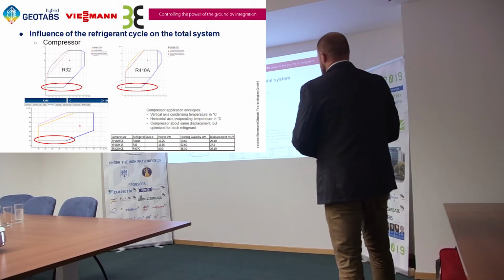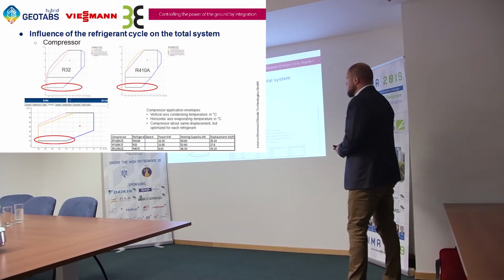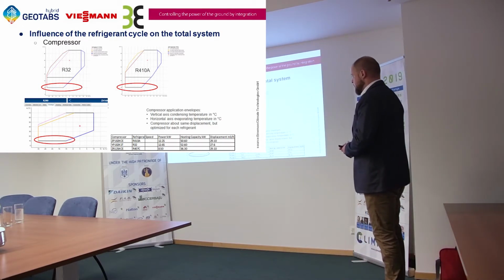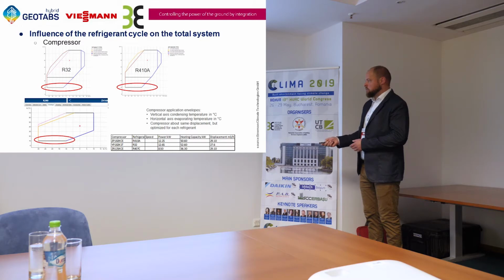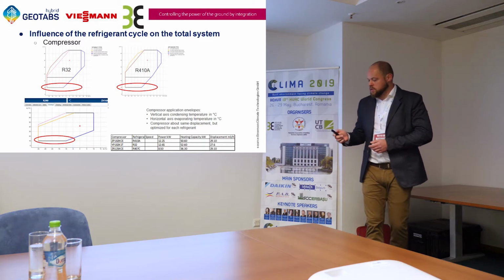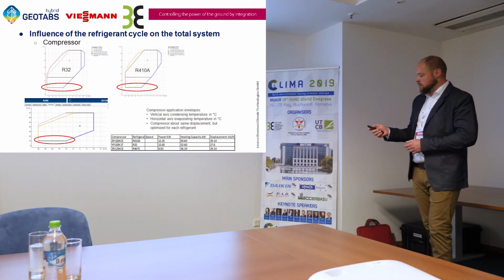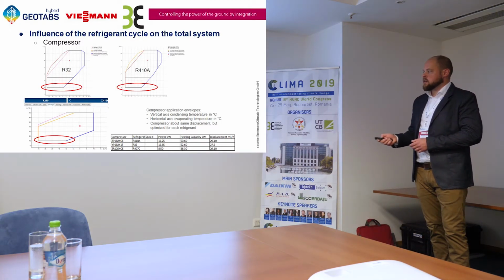These are other envelopes of different refrigerants with other compressor types. They are mentioned here below: different refrigerants, different compressor types. You can see that the power output and the displacement, so the heating capacity, is much lower with the R407, for example, in this case. But it's just an example of different working envelopes that we can use, and we have also added the one of propane inside this example.